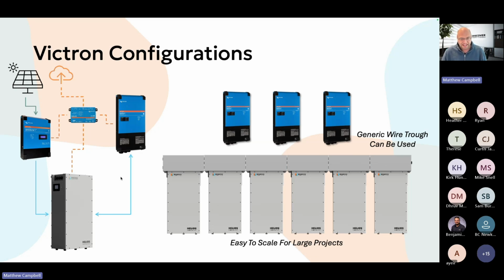If you're going to use the Victron - and I know our pictures here show our conduit box, but you could imagine instead of using a conduit box, you can use a generic wire trough along the top. You just cut out the bottom of the wire trough to match up with the top of the battery, then run all your conduit out the top and run all your wire through the cable trough. Again, that can make for a very clean, nice install using off-the-shelf wire trough, which is great.